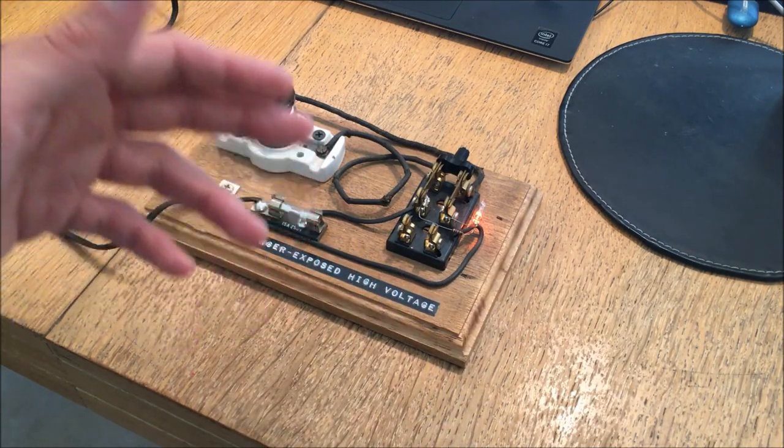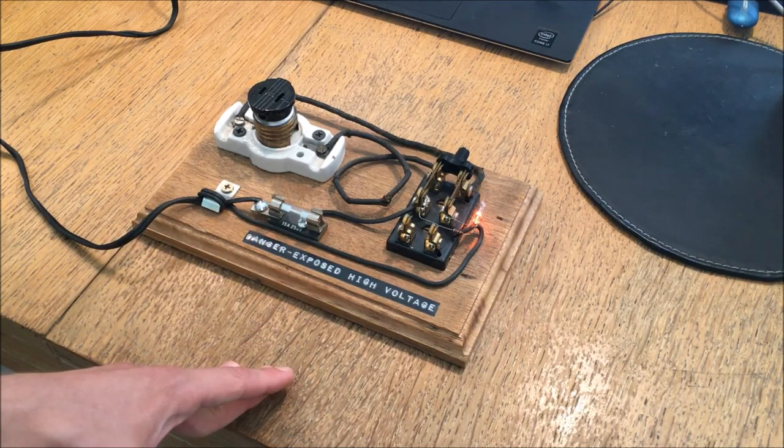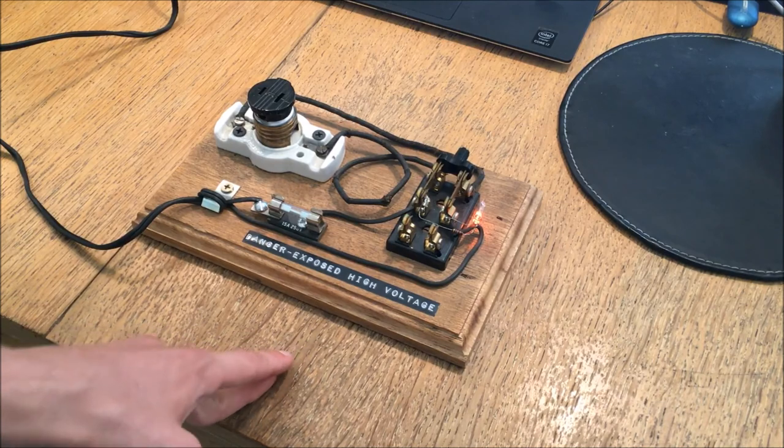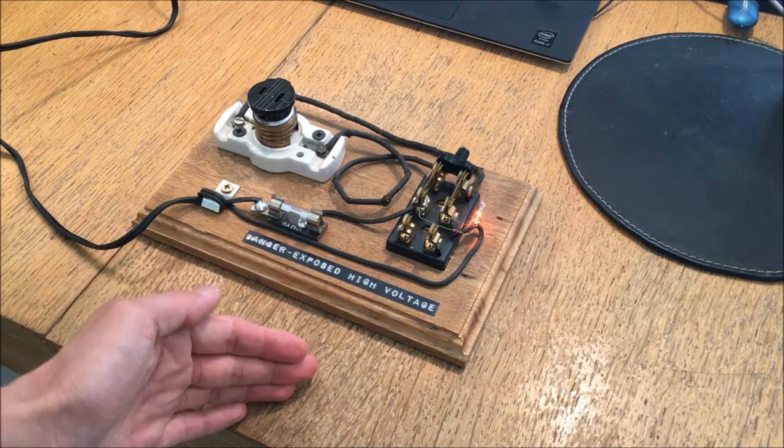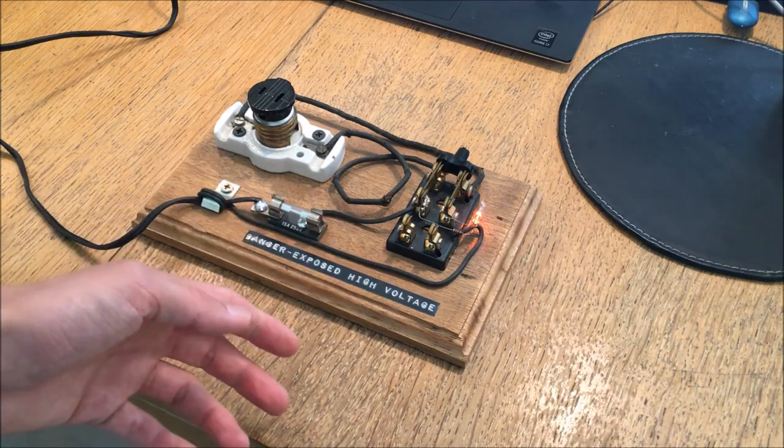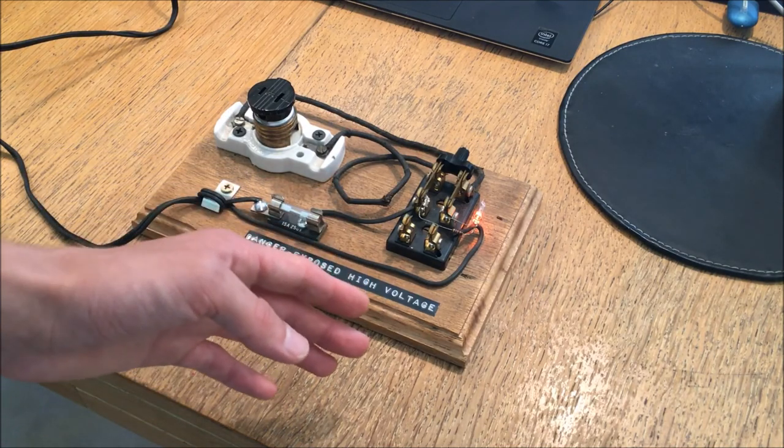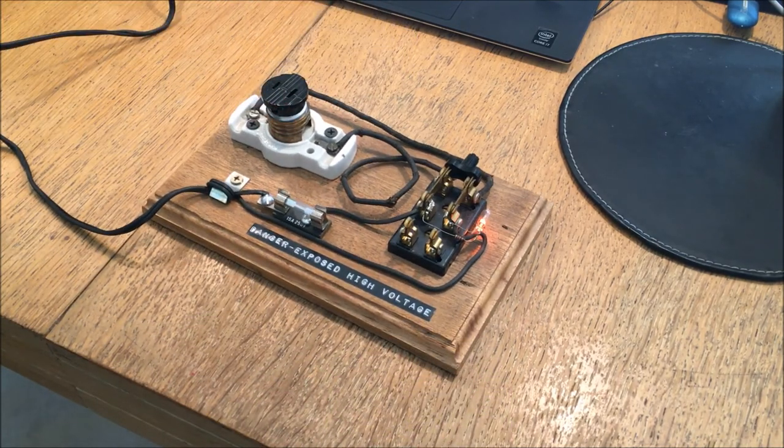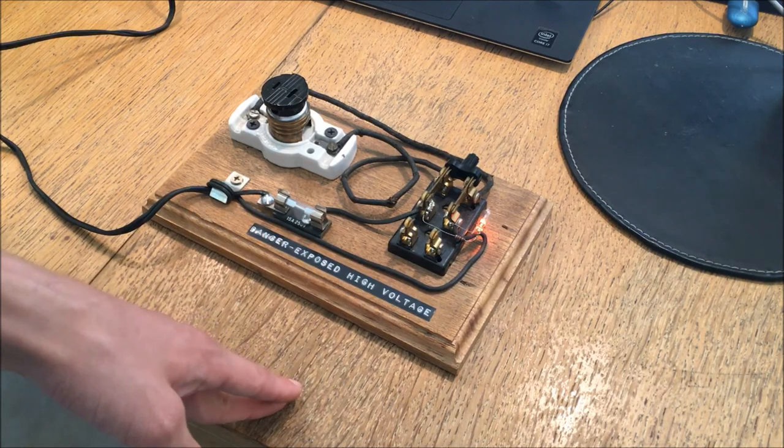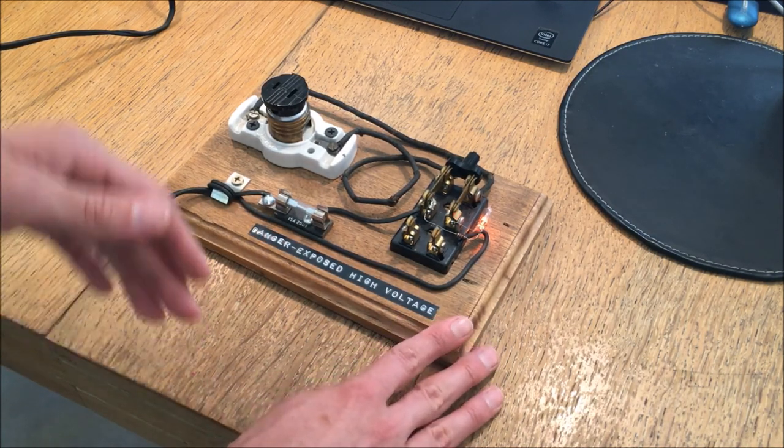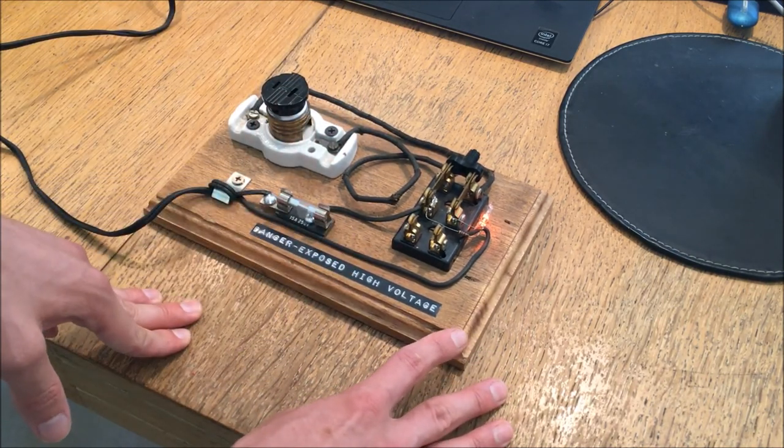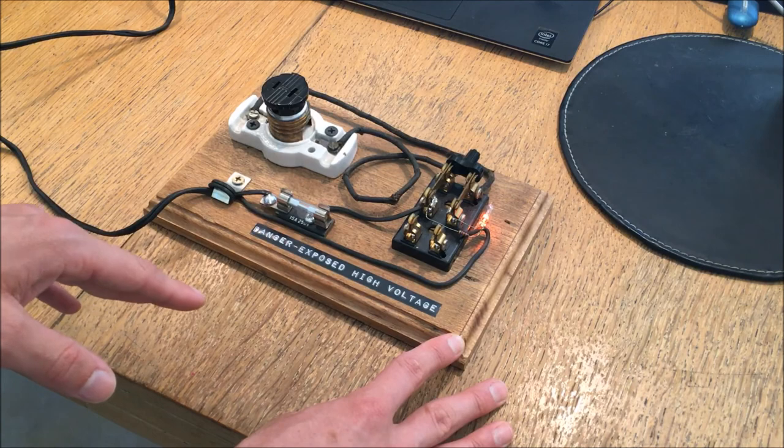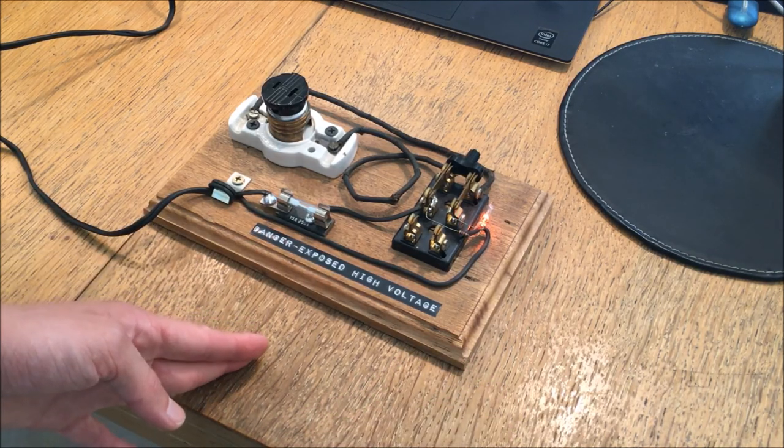However if I had two hands in the circuit and I touch two things in it at the same time that could be extremely dangerous because now you're conducting current across your entire body. This is why one of the best practices when working with live circuits is to the best of your ability only put one hand in the circuit at a time. Now sometimes this isn't entirely realistic because you may have to hold a board steady while you manipulate something on it, but if you have to keep your hands in the circuit be sure that whatever hand is not working on the active elements is as far away from the high voltage parts as possible and preferably if you can afford to do it turn off the power if you're going to be working on it.